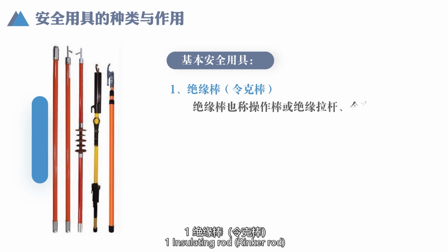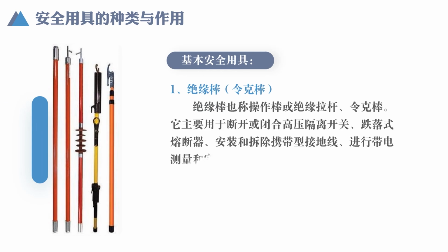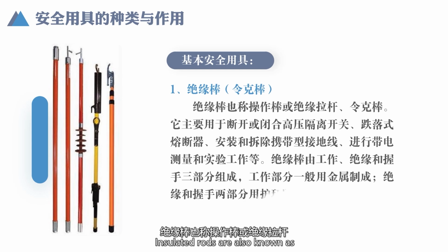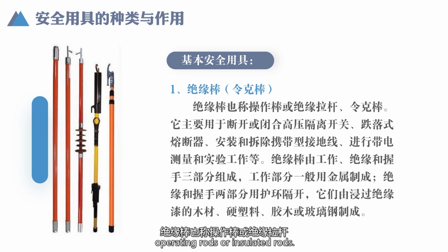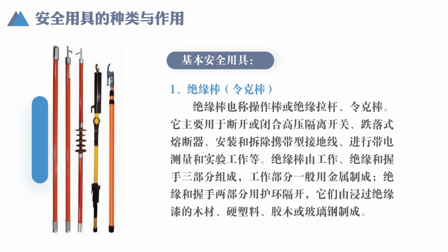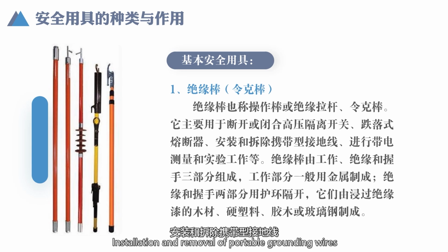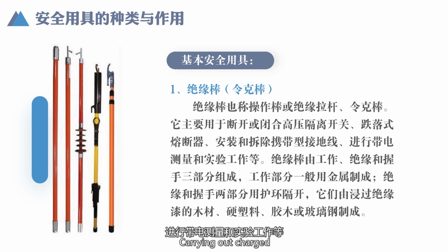1. Insulating rod, wrench rod. Insulated rod is also known as operating rod or insulated rod. Wrench rod. It is mainly used to disconnect or close high-voltage disconnecting switches, drop-out fuses, installation and removal of portable grounding wires, carrying out live measurement and experimental work, etc.